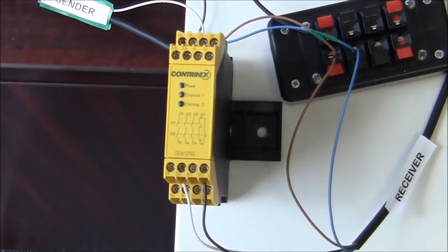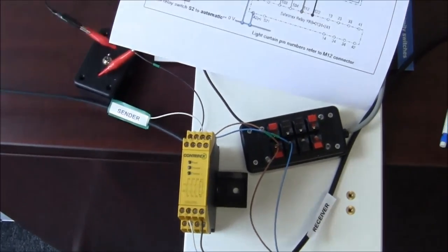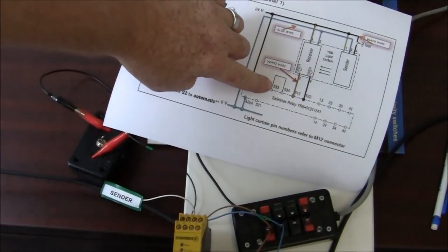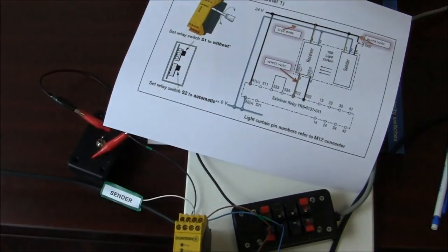Here I have everything connected. And the final connection that has to occur you'll see on the drawing right here, S33 and S34 is going to take a jumper wire. That allows for the automatic restart. I'm going to put that in and we'll power this unit up and give it a try.